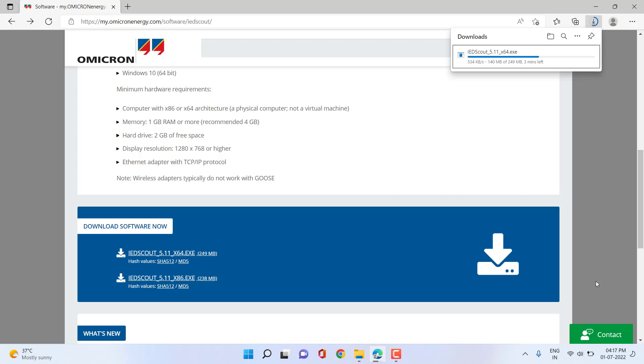We can also learn important information related to the IEC 61850 configuration that you build for your different IEDs in your projects with different configuration tools like the IED configuration tool and system configuration tool. You can import all different types of SCL files based on IEC 61850 part 6. There are six different types of SCL files supported by the standard, and all six can be easily imported into IEDScout. You can explore the IED configuration you built and different SCL files required for IEC 61850 client-server and GOOSE application testing.